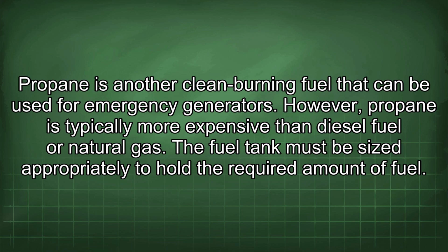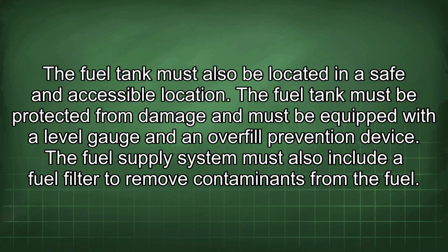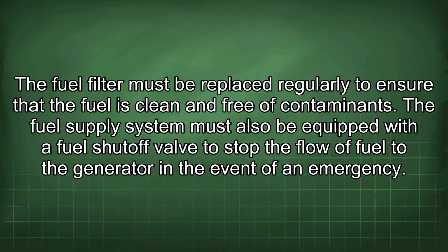The fuel tank must be sized appropriately to hold the required amount of fuel. The fuel tank must also be located in a safe and accessible location. The fuel tank must be protected from damage and must be equipped with a level gauge and an overfill prevention device. The fuel supply system must also include a fuel filter to remove contaminants from the fuel. The fuel filter must be replaced regularly to ensure that the fuel is clean and free of contaminants.